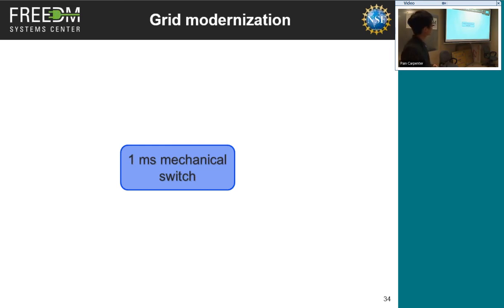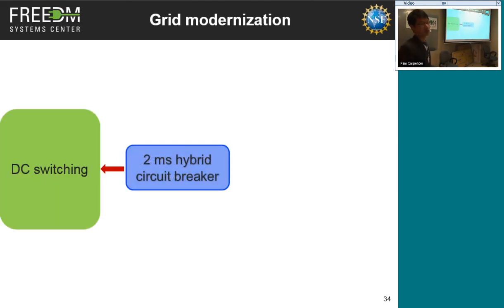We have this 1 millisecond mechanical switch, and based on that, I think we can develop a 2 millisecond hybrid circuit breaker. With this hybrid circuit breaker, we can do DC switching, no problem. But can we do AC? 2 milliseconds - what does that mean to an AC system? In a 60 hertz AC system, one cycle is 16 milliseconds, so 2 milliseconds is a small fraction of it. At the time the hybrid circuit breaker works, the circuit is actually considered as DC, so it does not matter for this fast hybrid circuit breaker whether it is an AC system or DC system.